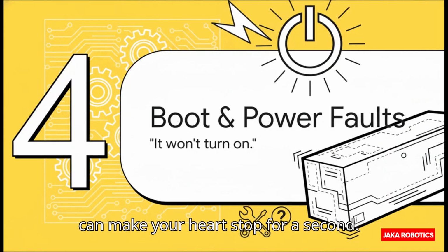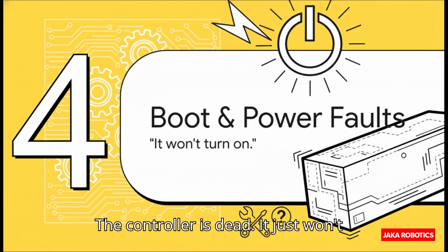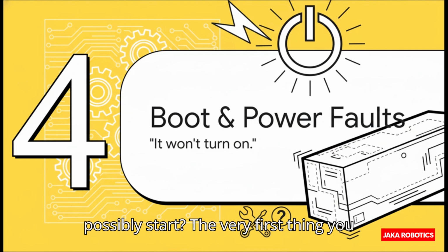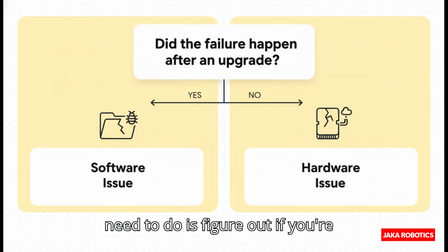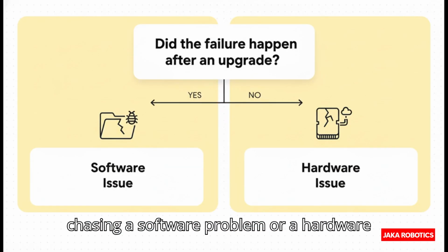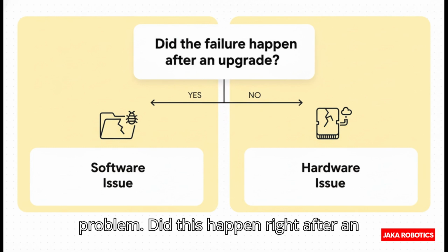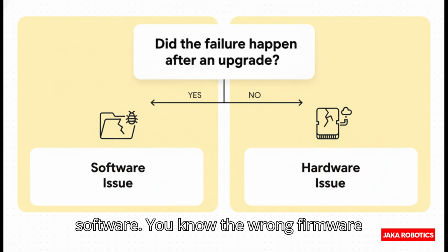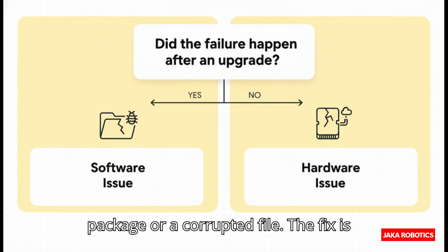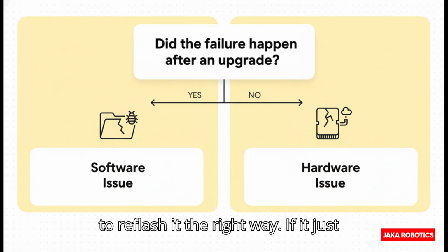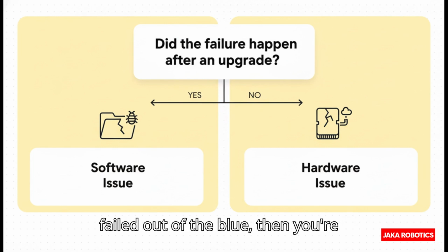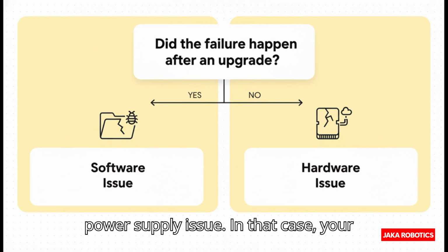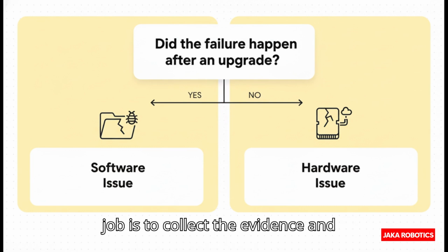All right, let's talk about the one that can make your heart stop for a second. The controller is dead. It just won't turn on, won't boot up. Where do you possibly start? The very first thing you need to do is figure out if you're chasing a software problem or a hardware problem. Did this happen right after an upgrade? If so, it's almost certainly software, you know, the wrong firmware package or a corrupted file. The fix is to reflash it the right way. If it just failed out of the blue, then you're probably looking at hardware, a bad SSD, a power supply issue. In that case, your job is to collect the evidence and escalate.